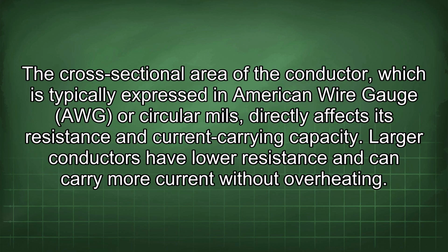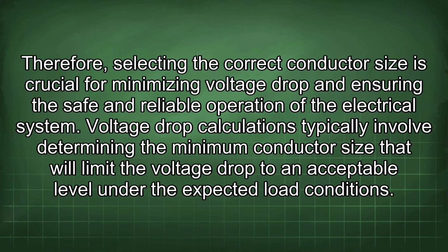The cross-sectional area of the conductor, which is typically expressed in American wire gauge (AWG) or circular mils, directly affects its resistance and current carrying capacity. Larger conductors have lower resistance and can carry more current without overheating. Therefore, selecting the correct conductor size is crucial for minimizing voltage drop and ensuring the safe and reliable operation of the electrical system. Voltage drop calculations typically involve determining the minimum conductor size that will limit the voltage drop to an acceptable level under the expected load conditions.